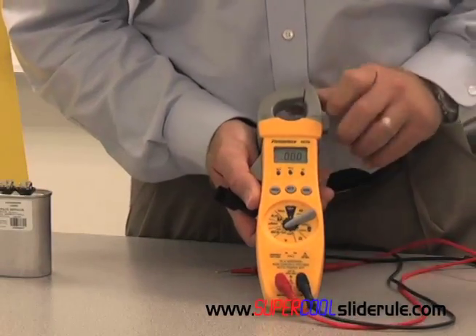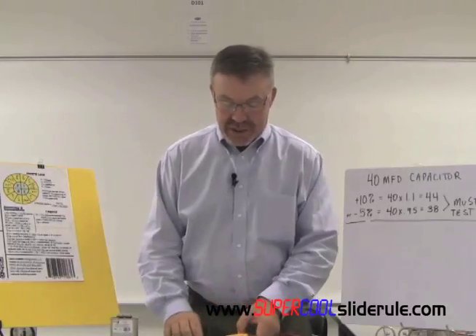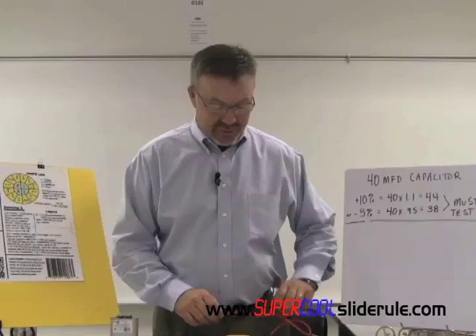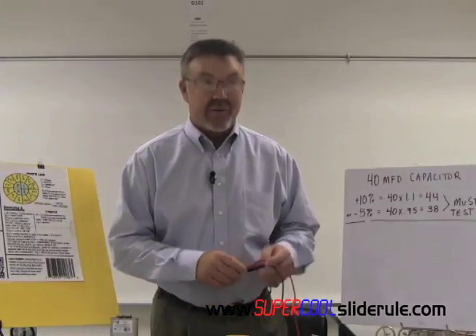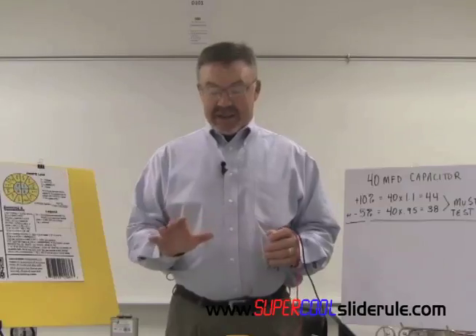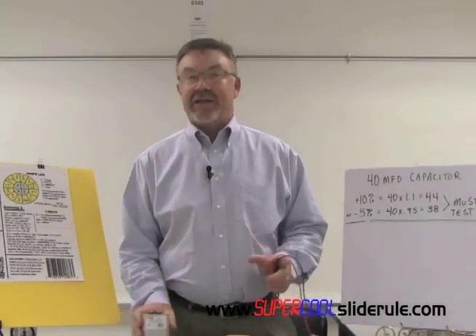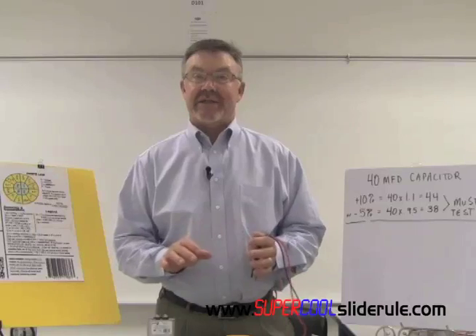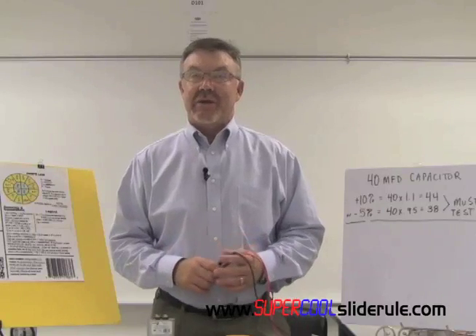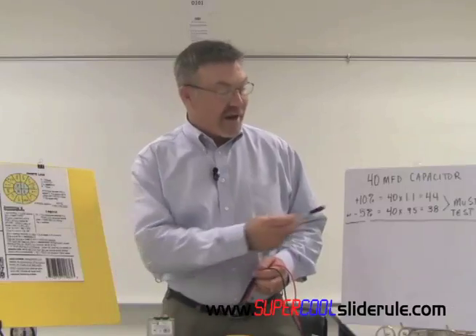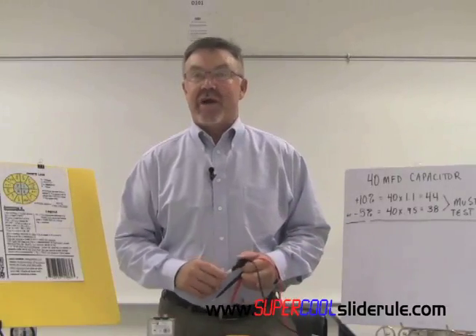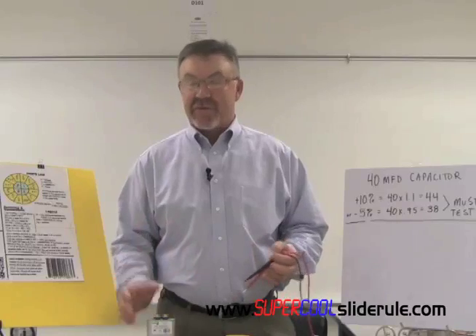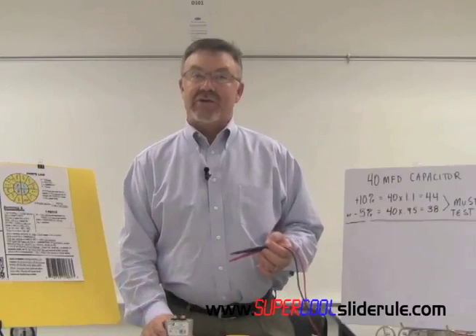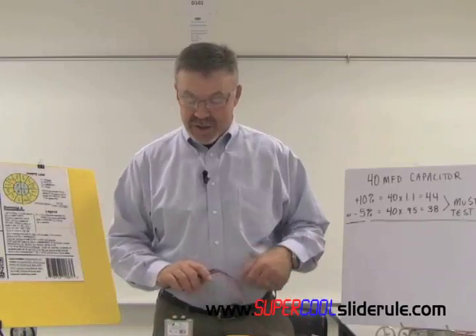I'll do that now. Now, do not use an analog tester where you look for the spike. That does not work. That's not the proper way to do it. Get a tester. If you're going to do this, get the right tester. You need a tester that will test capacitance. The reason for that is it's extremely important that you are within your 5 to 10% parameters in order to protect your compressor and your motor to make them work properly.